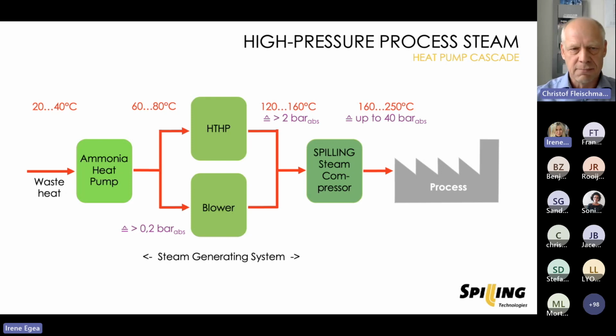And from this low pressure steam level, 2, 3, 4, 5 bar on, now, for example, piston compressors like from Spilling or other mechanical vapor recompressor units can compress then the steam to higher pressure levels, like it's required for industrial processes, up to 10 bar, 15 bar, 20 bar, even to 40 bar, like shown here.